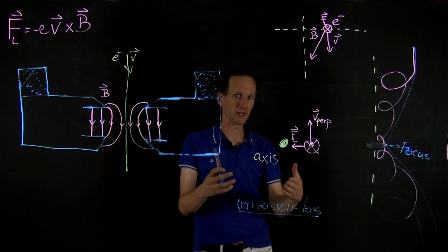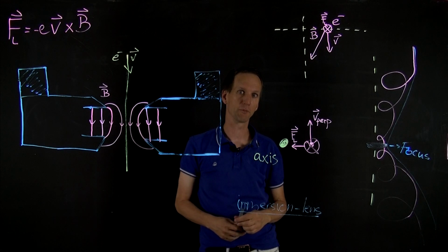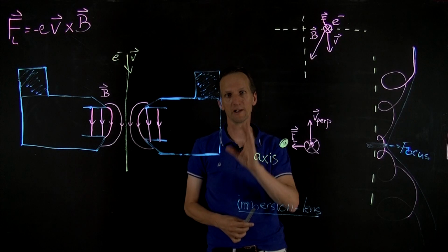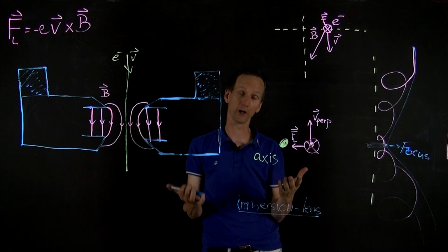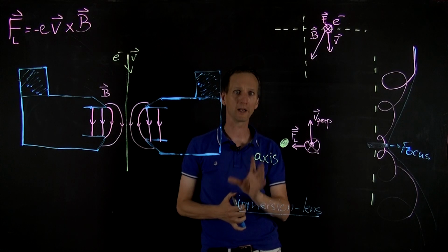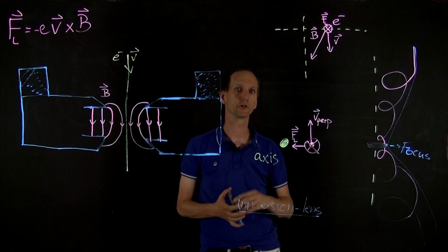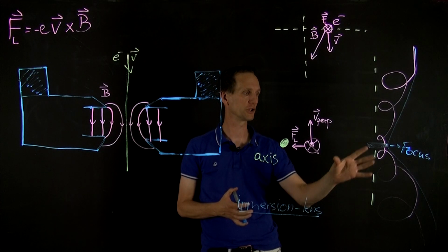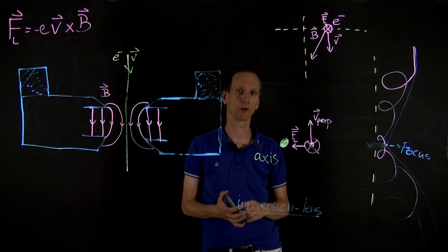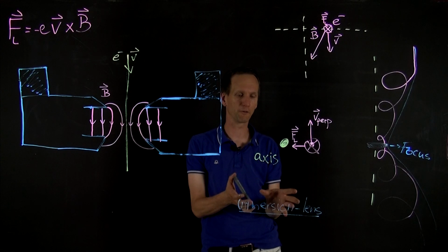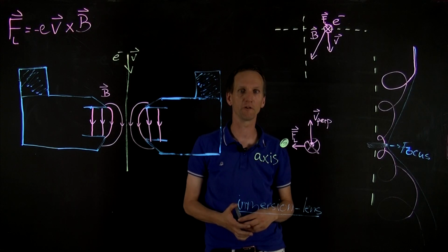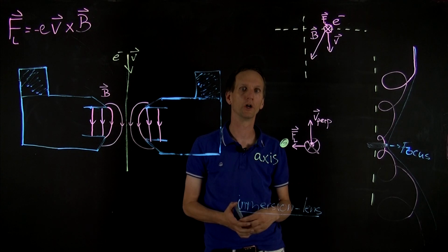So the fact that often magnetic lenses are used in electron microscopy and can also be immersing the sample means that we can never use magnetic materials inside an electron microscope. So also the sample holders should not be magnetized or of magnetizable material, because otherwise they will also feel the force exerted by the magnetic lenses and thus start to move inside our electron microscopy chamber. Also, of course, magnetic fields applied on the sample or by the sample will distort our focusing effect and thus deteriorate our imaging.